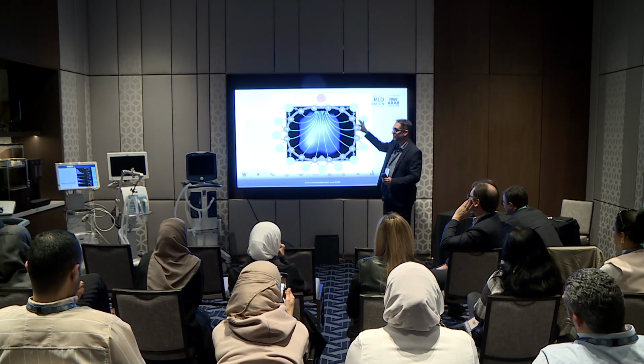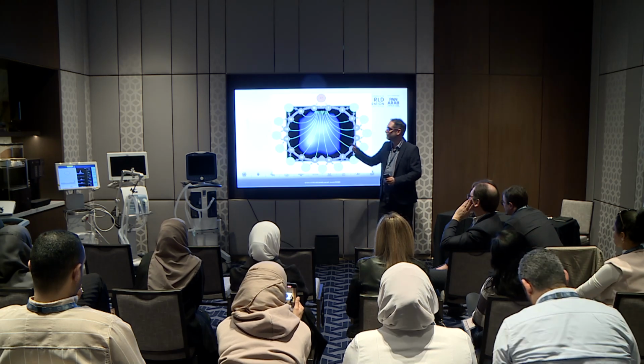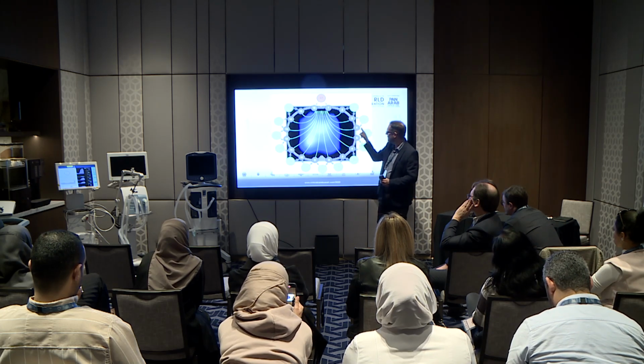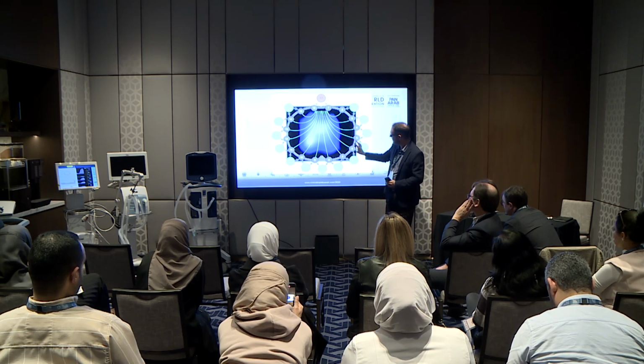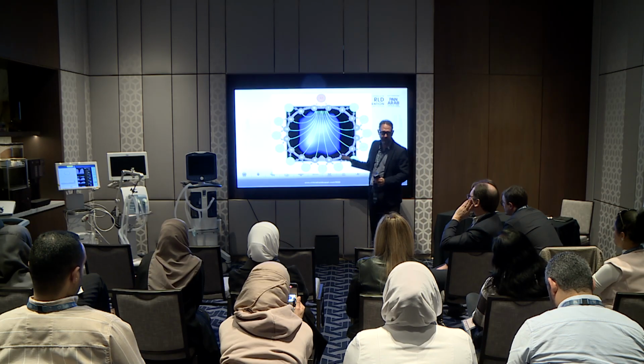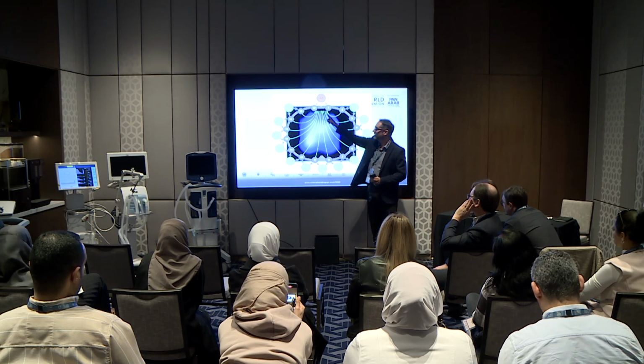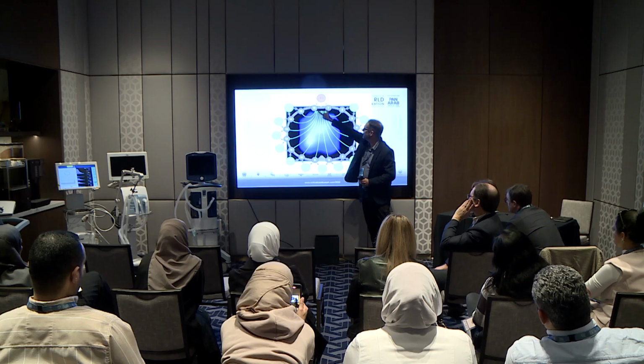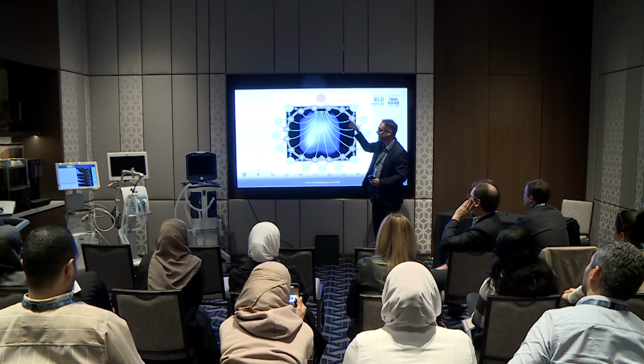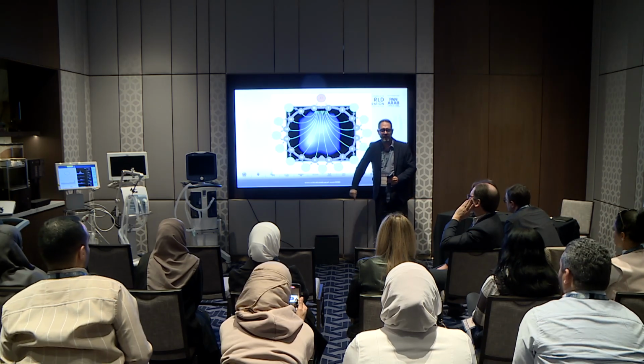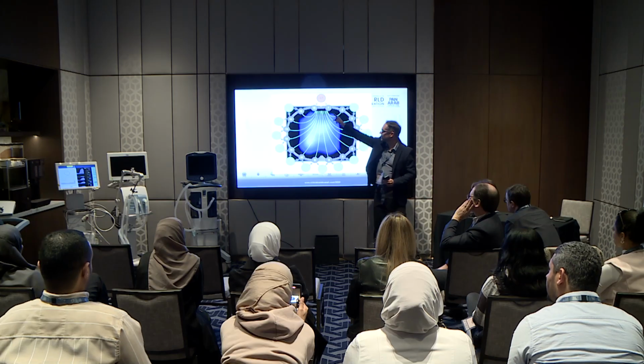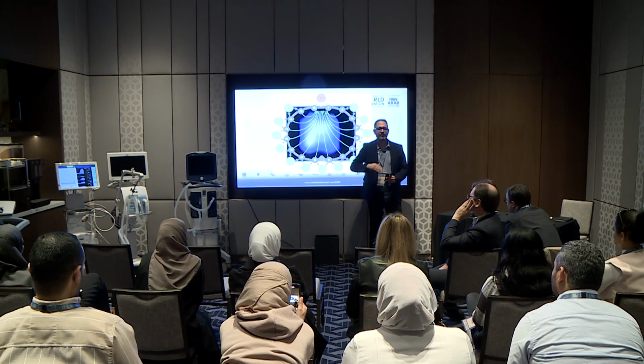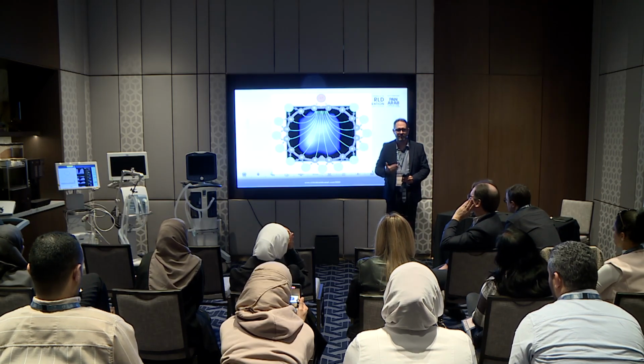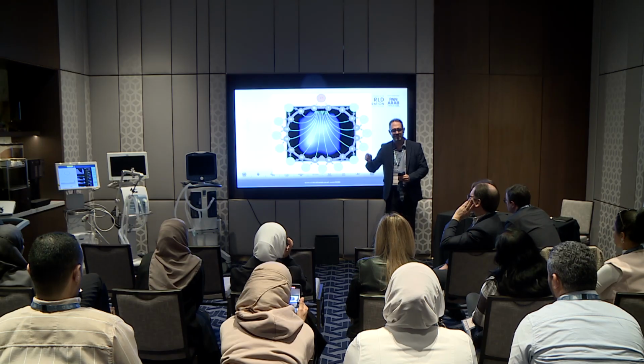It measures the impedance, which is just the resistance. So the resistance of that current going to each of these leads, each pair is measured the resistance from here. It goes around the chest. Then it moves the reference lead to here. And it does the same thing again, okay? And once it reaches around the chest once, you have a tomographic slice, EIT, electrical impedance tomography.